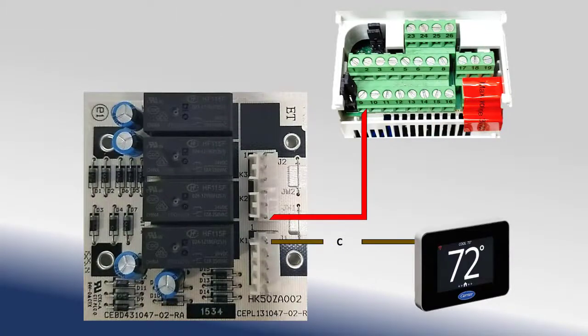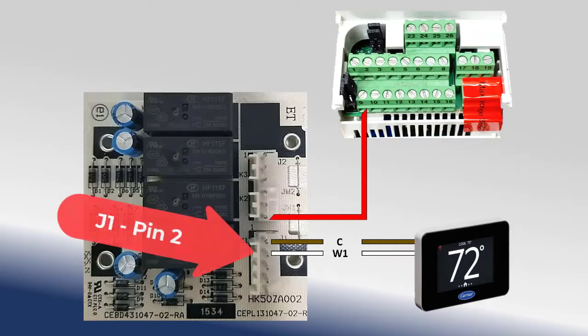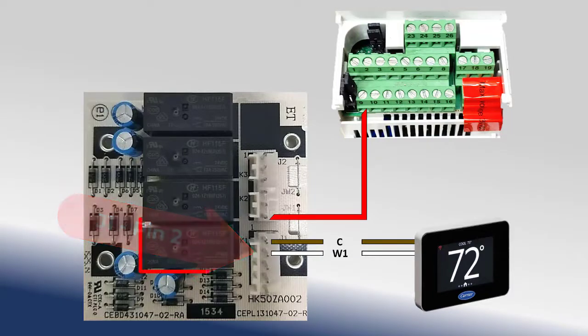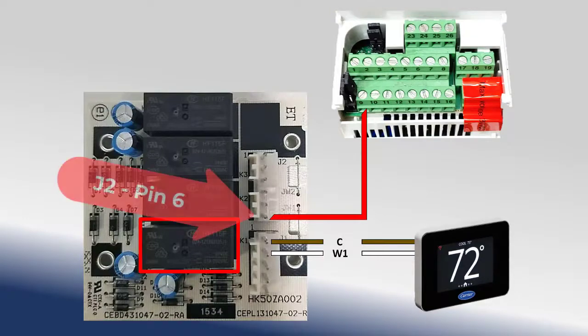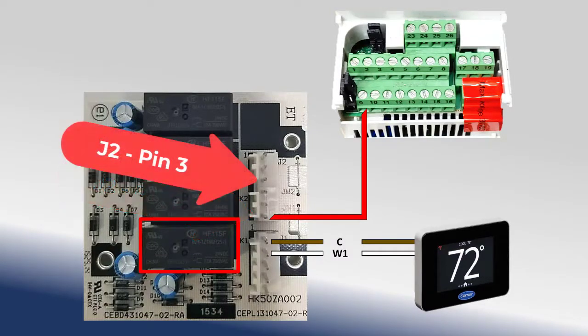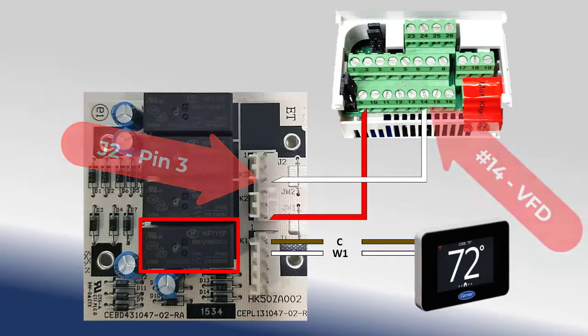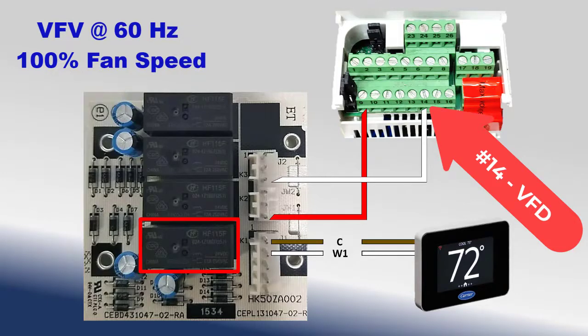During heating operation, an internal path carries the 24-volt AC W1 signal to the fan control board at J1, pin 2, in turn closing relay K1. When the K1 relay is energized, the 24-volt DC signal from J2 terminal pin 6 is closed to J2, pin 3, which is returned to the VFD at terminal 14. This initiates a command for the VFD to come to 60 Hz, or 100% of fan speed.